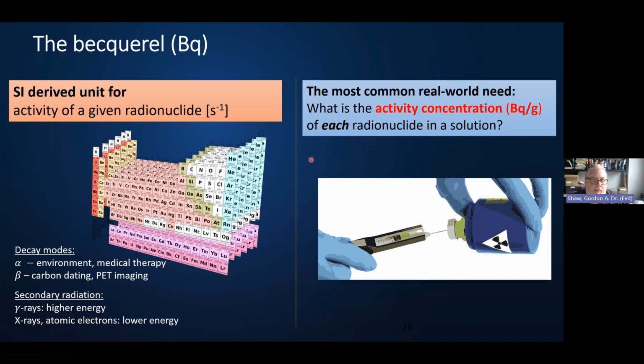In the real world, the most common way that these standards are disseminated is using a liquid solution of a radionuclide salt. So the radionuclide element or isotope is dissolved in a liquid, and then the liquid is measured out by mass. And for a given amount of material, the given mass, a radioactive activity in becquerels is specified, so that when this standard reference material is used in the final calibration environment, the SRM can be dispensed by mass and then used to determine the total radioactivity in becquerel. So these SRMs come with an activity concentration in units of becquerel per gram.